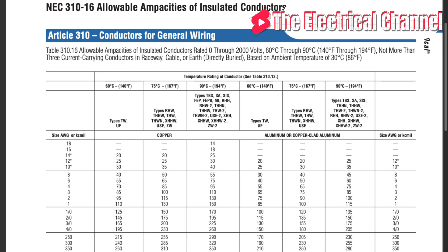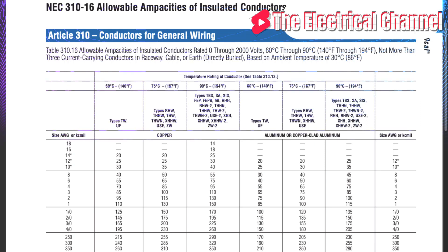Also, depending on the insulation, the ampacity changes as well. So for example, the THHN number 12 has a max ampacity of 30 amps. The number 10 has a max ampacity of 40, and the number 8 has a max ampacity of 55.